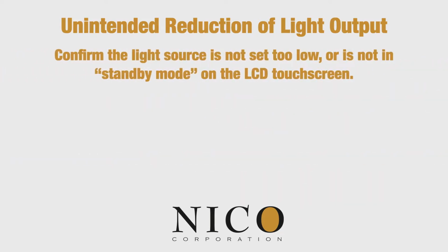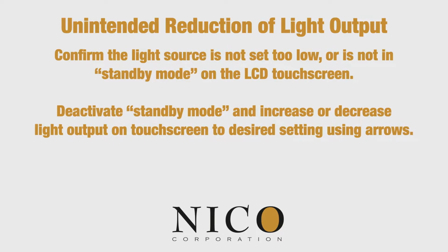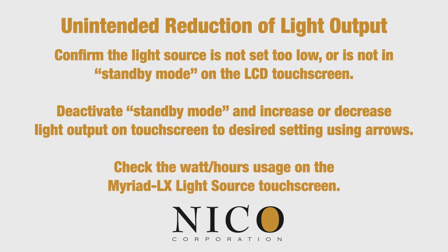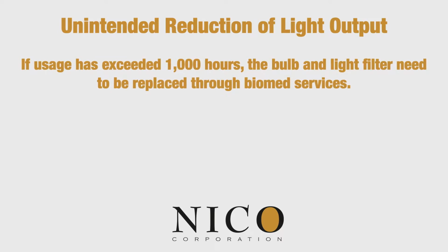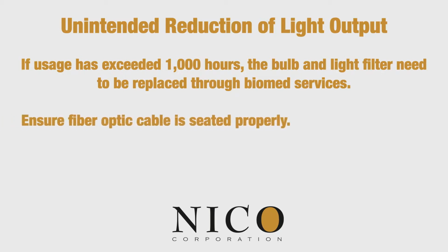Confirm the light source is not set too low or is not in standby mode on the LCD touchscreen. Deactivate standby mode and increase or decrease light output on touchscreen to desired setting using arrows. Check the watt-hours usage on the Myriad-LX light source touchscreen. If usage has exceeded 1,000 hours, the bulb and light filter need to be replaced through Biomed services.